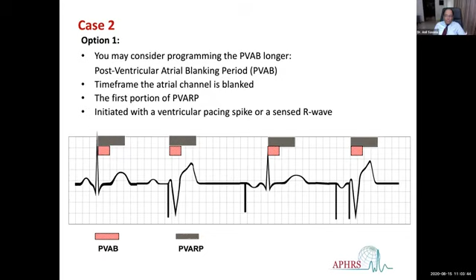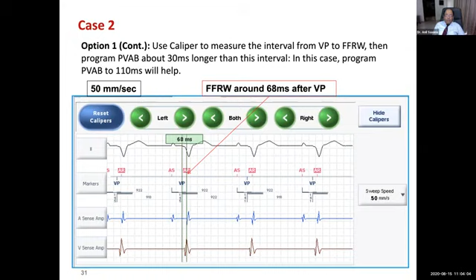So what we need to do is measure from the V pace to the far-field R-wave, and that interval in this example is around 68 milliseconds. So we have to program our PVAB, that is post-ventricular atrial blanking, to be more than that, and that will solve the problem. But it is very important to take care at the time of implantation that we should not see the ventricular signal at all in the atrial channel.